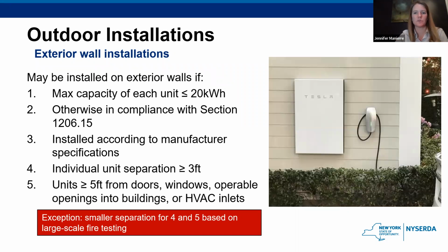Okay. Still in outdoor installations, for exterior wall installations, you're not going to be putting any units on there that are greater than 20 kilowatt hours. There can be multiple of the same units, but they need to be separated by at least 3 feet. And all of them need to be at least 5 feet away from doors, windows, other openings into the building. Once again, there's that possibility for an exception based on large-scale fire testing. So the large-scale fire testing might show that it's safe to put the units within 2 feet of each other instead of 3, or perhaps they can safely operate within 4 feet of doors and windows instead of 5.